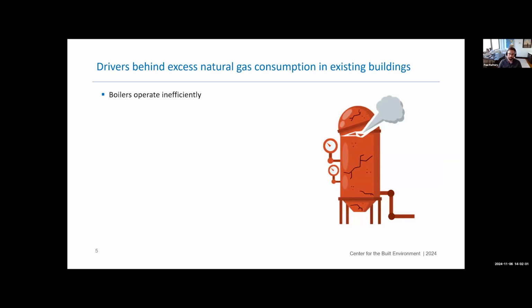The first one is the actual boilers themselves don't operate as efficiently as many people would assume looking at nominal efficiency. These are usually older pieces of equipment, very oversized with poor capability to turn down to low output or low loads. And we did some early work that measured really poor efficiency of these units in the field, and we wanted to go out and see how prevalent of an issue that was. And that drives a lot of wasted gas consumption.